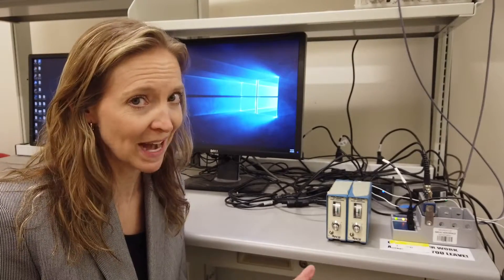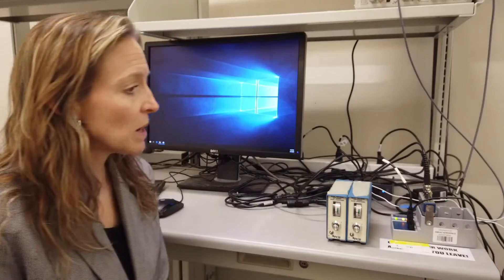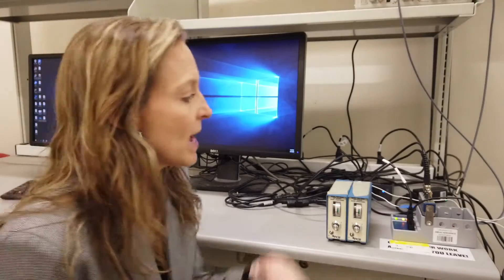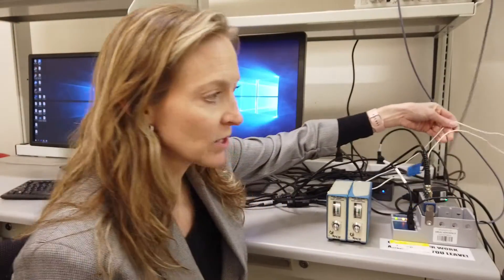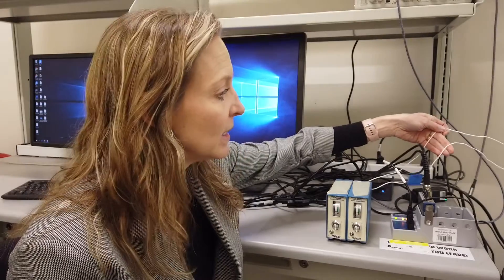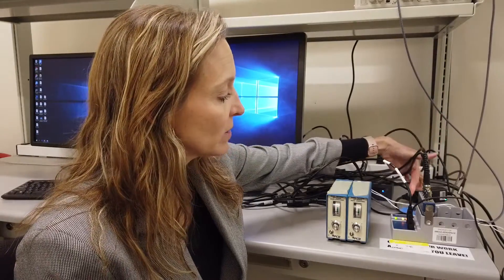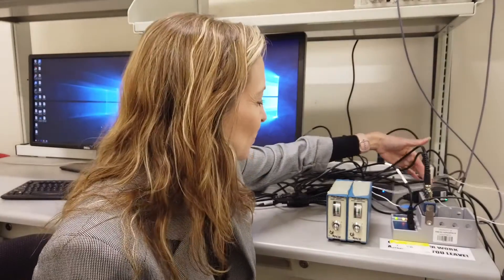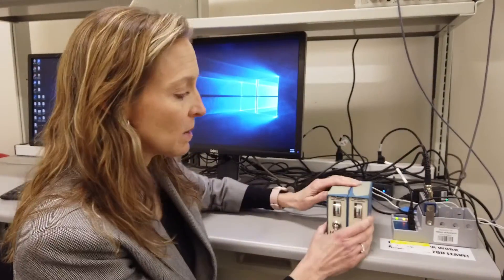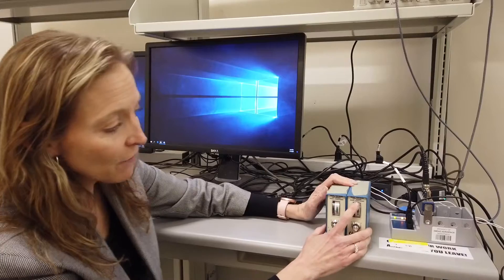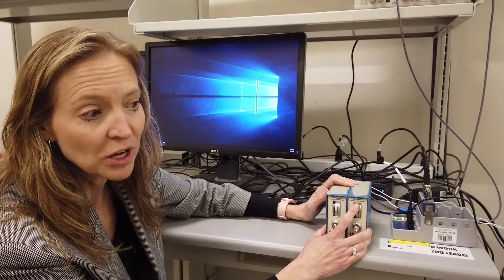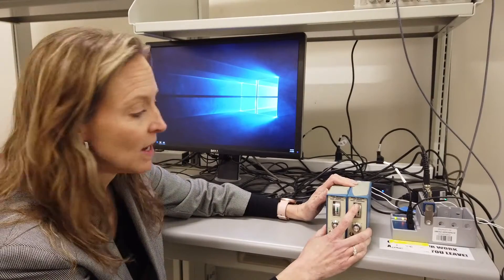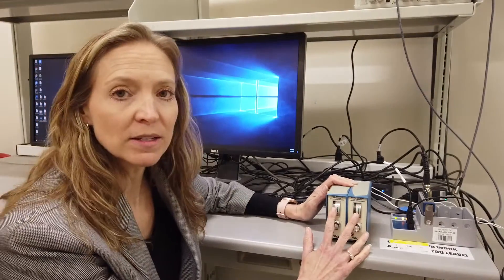You want to double check that there are two white wires coming from each of the load cells on the static test stand, each labeled channel 0 and channel 1 respectively. Those should be plugged into the back of the 484 signal conditioning boxes. These signal conditioning boxes are necessary to provide the proper voltages and current levels to the dynamic piezo crystal sensors.